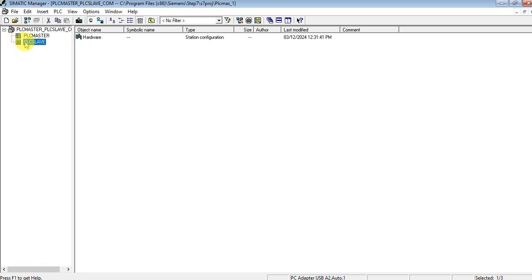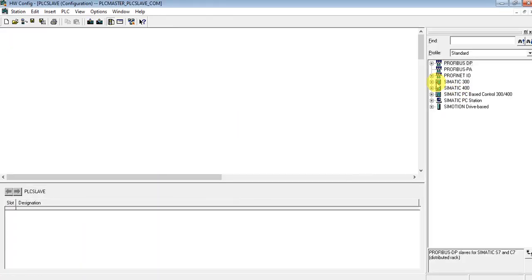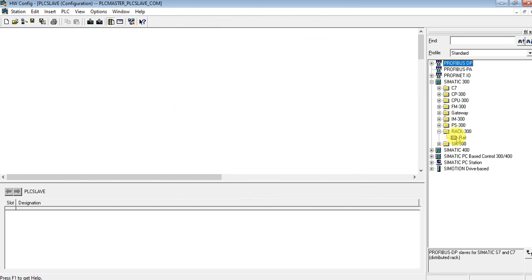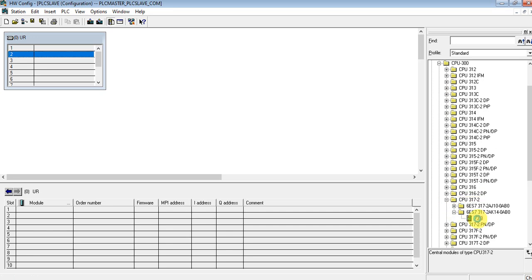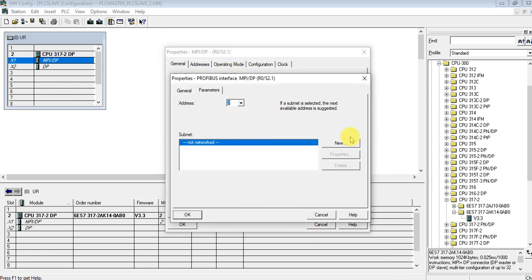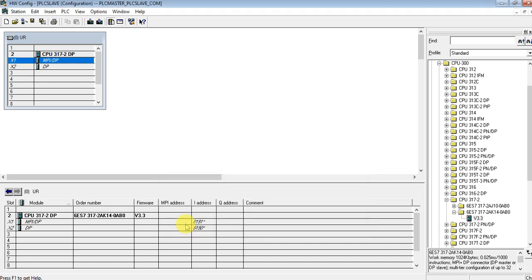Let's do the hardware configuration now. Let's insert the rack and then insert the CPU. My CPU is 317-2DP. Let's create the PROFIBUS network — PROFIBUS 1. We have to select this CPU as a slave, and we're done. Let's save this configuration.